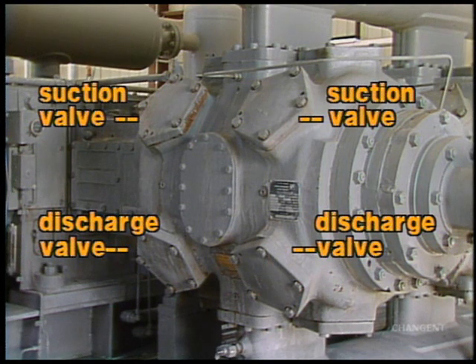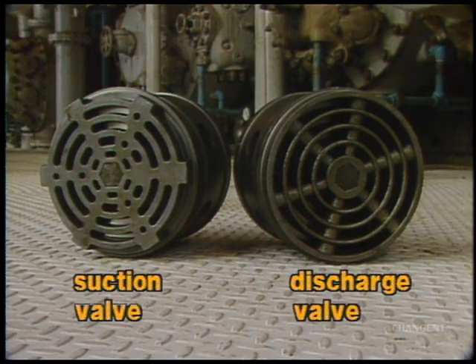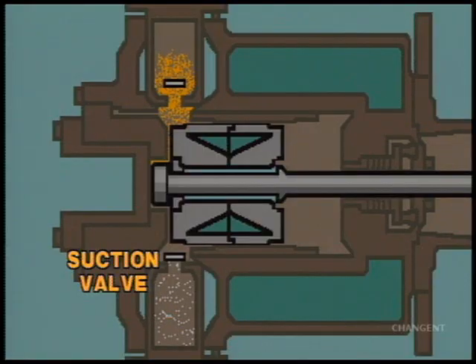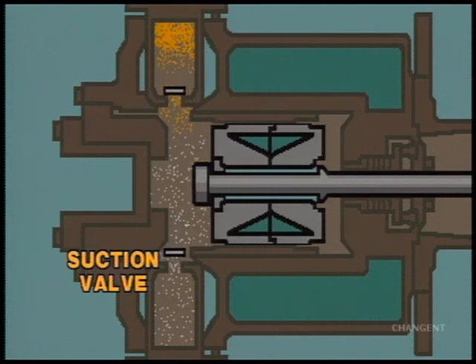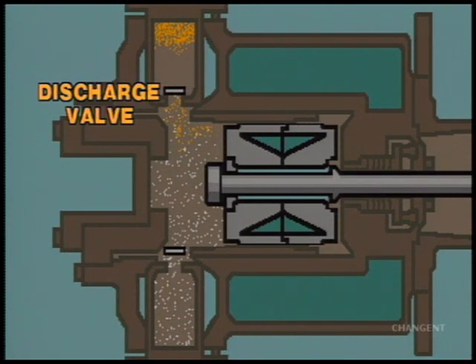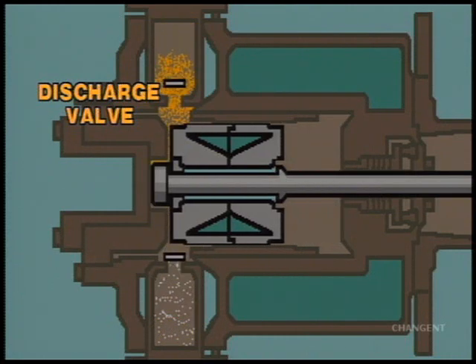Each cylinder also contains two sets of valves: suction and discharge. These valves look similar, but gas travels through them in only one direction. As suggested by their names, a suction valve allows gas to enter the cylinder for compression, while the discharge valve lets the compressed gas leave the cylinder.